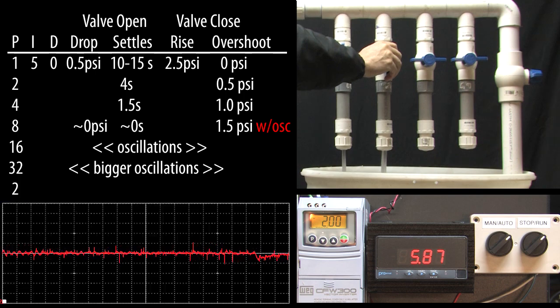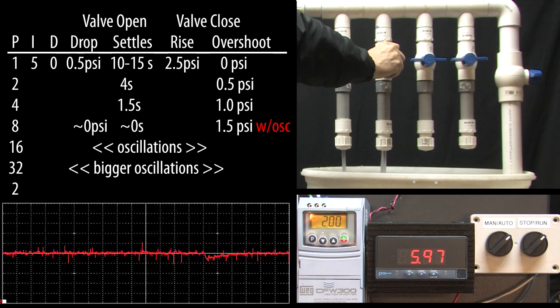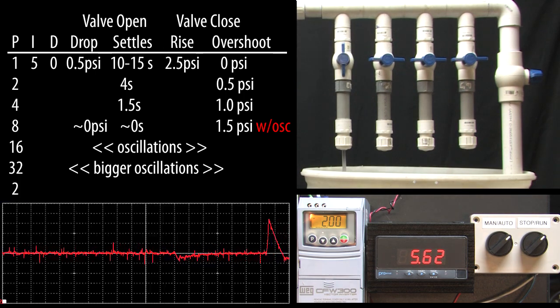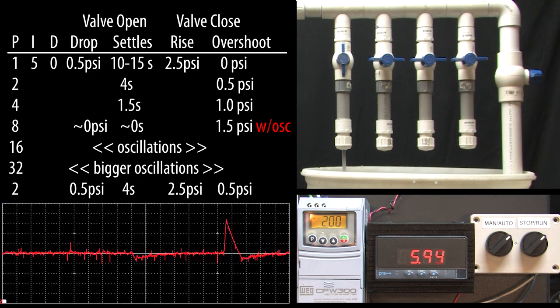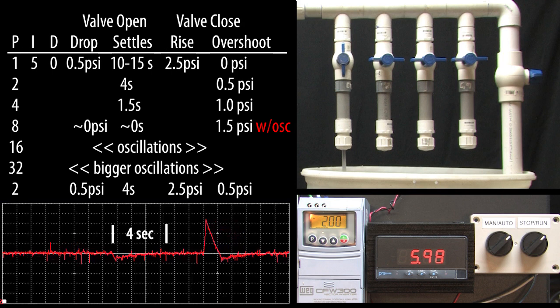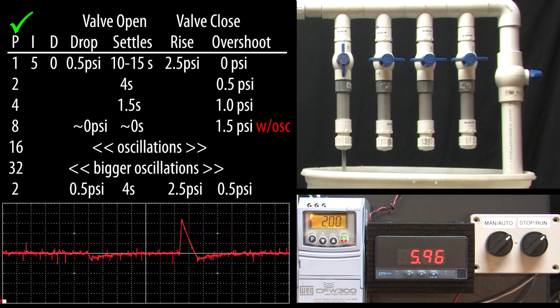I'll open and close the valve and sure enough we're back to our super stable, reasonable response. I kind of like this because it's faster than the 10 to 15 seconds we were seeing with the default PID values and the overshoot here isn't any worse than the pressure drop here. That's a pretty good compromise. OK, that gives us a good feel for how P affects things.